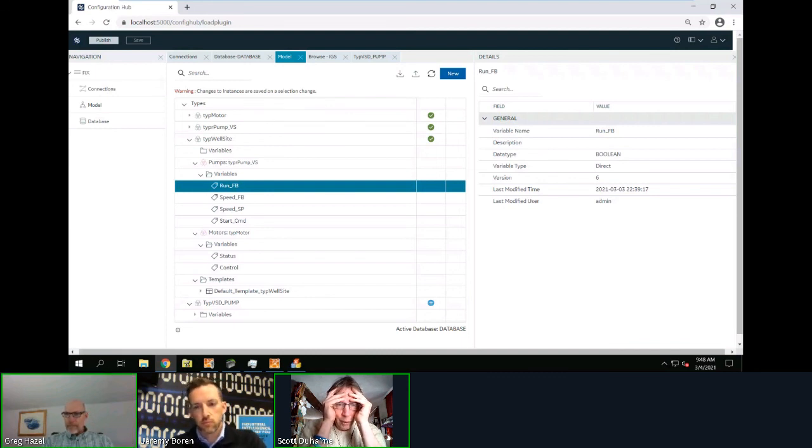But what we did was we locked down the install and the use of the SCADA to those that are on an approved Windows directory or a Windows group. So when you install in secure mode, you've got to make sure the users belong to that particular group that you've approved. And so we've locked down things like access to shared files and folders, registry settings, and shared memory.